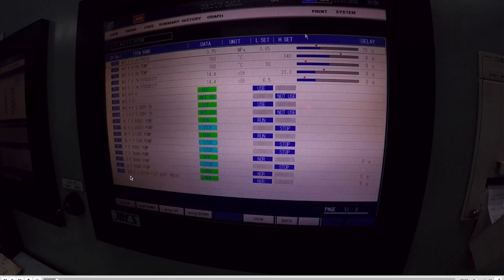And also here we have managing of the fuel oil discharge filter differential pressure. In case something goes wrong here, we have a high differential alarm, and we must go down directly. And also we can check the pressure here. If the pressure goes down, that means our filter is dirty and we should change to manual filters to bypass filtering, so we will protect our diesel generators and will not have any reduction of speed or some kind of blackout.